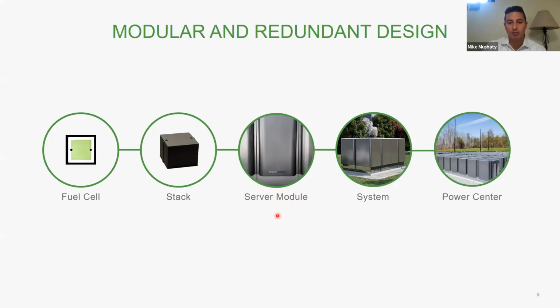We aggregate multiple power modules to generate a system. Our system sizes are 200 kilowatts, 250 kilowatts, and 300 kilowatts. And we will take those system sizes and parallel them together to achieve multi-megawatt scale. So for example, if you need a megawatt worth of Bloom Energy power, we would parallel together 4 250 kilowatt systems. If you need 3 megawatts of Bloom Energy power, we would parallel 10 300 kilowatt Bloom Energy servers. So that's how we go about taking a 25-watt tile and turning it into a multi-megawatt power plant.